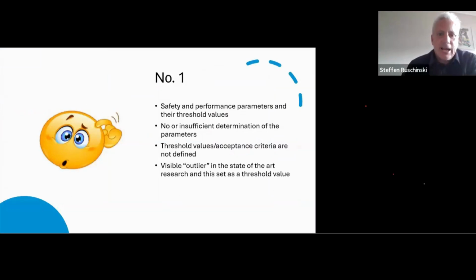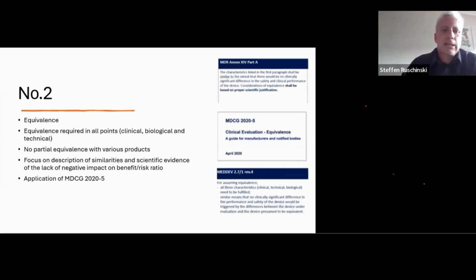Safety and performance parameters and threshold values are not determined or are insufficient, or the acceptance criteria or values are not defined. What is often happening is that in the state-of-the-art research you see a visible outlier, and the manufacturer takes this as a threshold value, and this will not be accepted by notified bodies. Equivalence, just for all the people joining this call from the States, is viewed differently than the FDA's equivalence. Here, equivalence is required in all points, meaning clinical, biological, and technical equivalence, and not a partial equivalence with various products. So we have to focus on the description of similarities and scientific evidence of the lack of negative impact on the benefit-risk ratio, which is all described in the MDCG 2020-5.